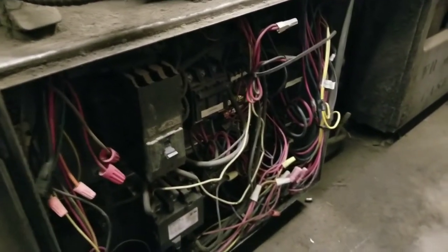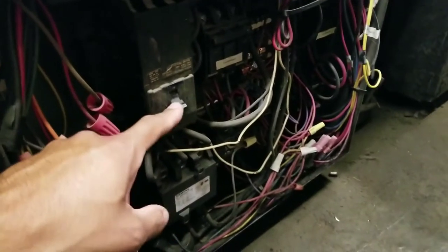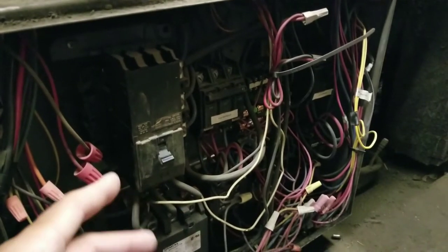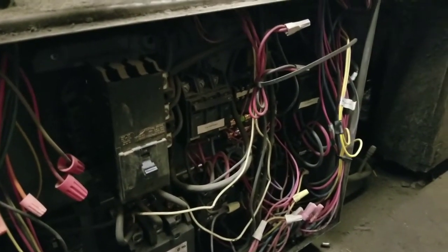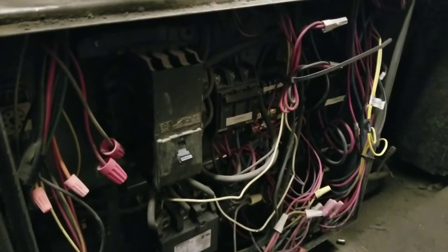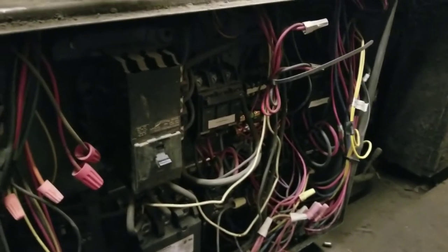This is what I was tearing apart. What's been going on is they had this happen a couple times already. This is my first time here — there's been another guy here before. What happened was the breaker tripped to the main breaker for this compressor. The manager reset it before we walked in the first time, so I couldn't figure out why it tripped. That was the first call. I'm back here on the second call — it's like midnight right now — and the breaker tripped again. I came and did a little bit of inspection.